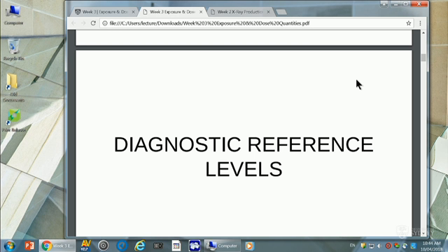Well, that's what happens. We showed it in Dublin. It's been shown in the UK. It's been shown in Germany. If you do a dose survey, you will be astounded by the variation of dose that's possible if the same person goes into different hospitals. It can be down to the energies, the mAs that you select. It can be down to the digital receptor. It can be down to the distance you use. It can be down to the protocol you use. There can be a load of reasons for that happening. It can be down to the radiologist that you've got who really wants a high-dose image so they can see all the exquisite detail, even though it contributes nothing necessarily to the diagnosis.